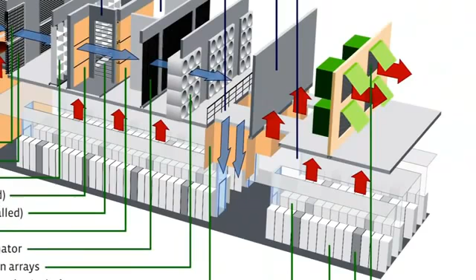So in this particular case, the air has come down this shaft. I showed you above us the area with the railings around it. The air comes down the shaft, it floods the cold aisles in the data center, and you can feel it's about 72 degrees right now. It goes through the servers into the hot aisle, and what you can see behind you over here, there's plexiglass. The air goes back up into the shaft.